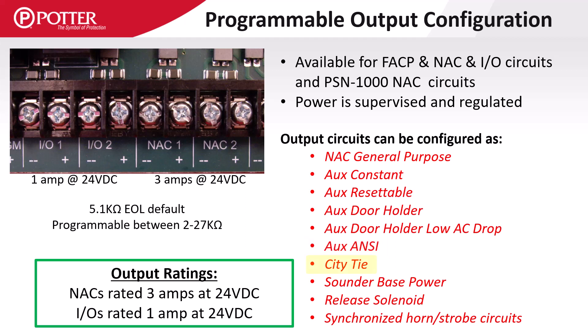The city tie output provides connection to municipal boxes. Sounder base power is the specialized power output for sounder bases only. This power circuit will pulse on and off in a temporal 3 or temporal 4 pattern to provide signaling for either fire or CO alarms. The pulsing characteristics of this circuit make it unsuitable for use with other devices.